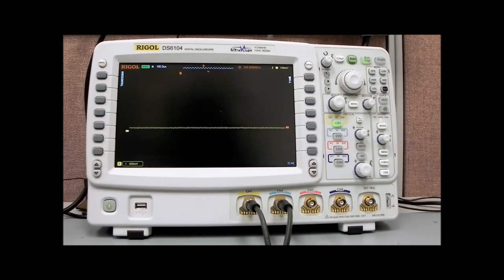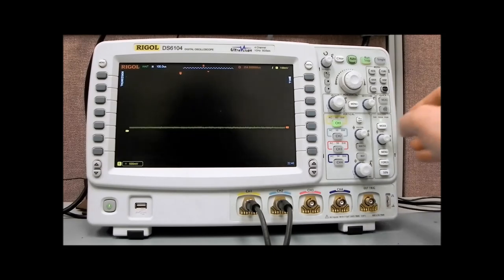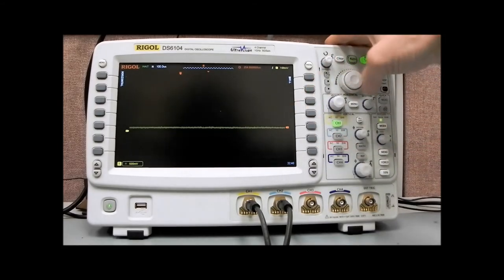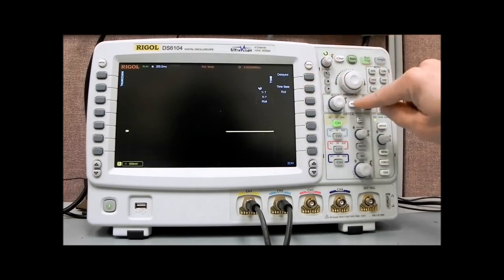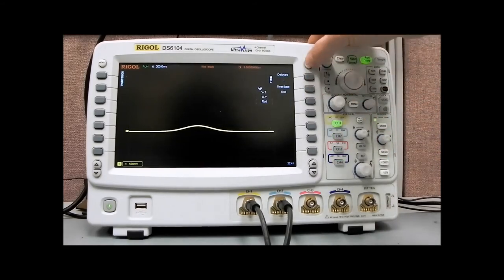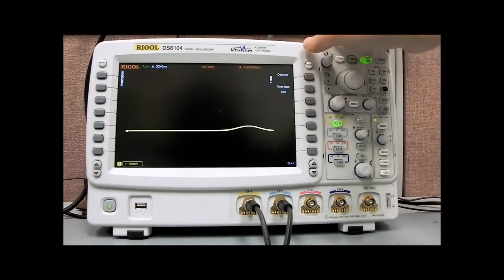For slower-moving signals, the DS6000 also has a roll mode. What I have here is a function generator set up to perform a waveform that's like a cardiac or EKG signal, and I have it set to 100 millihertz. Right now we're triggering on it, but you can't really see a whole lot of detail. What we can do is enable roll mode, which is in the horizontal time scale, horizontal menu. We can select roll.